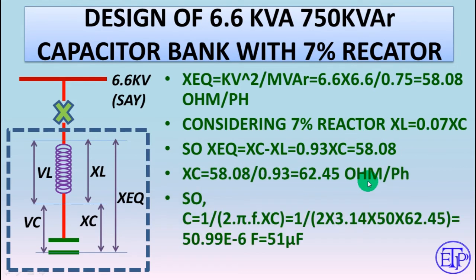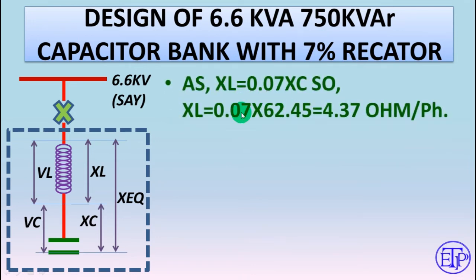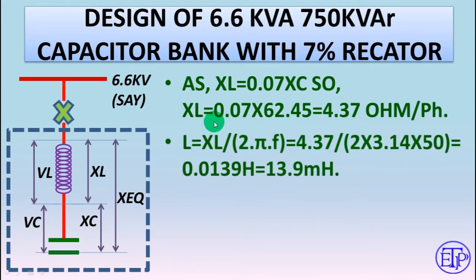For a 50 Hz system, the capacitance is 51 microfarads. XL equals 0.07 × XC = 4.37 ohms per phase. L equals XL / (2πf), which for a 50 Hz system gives 13.9 millihenry.